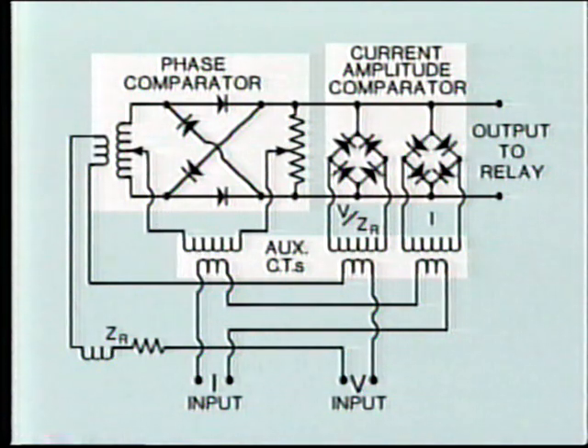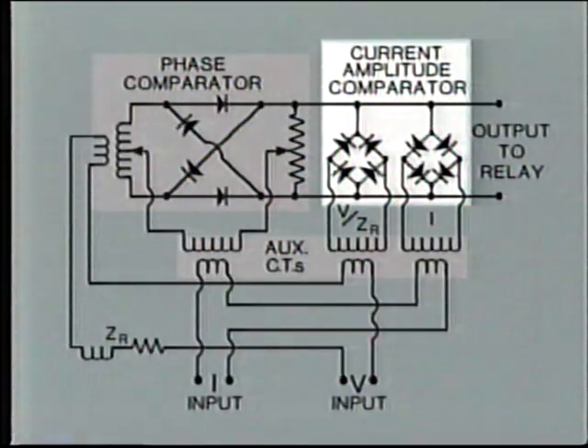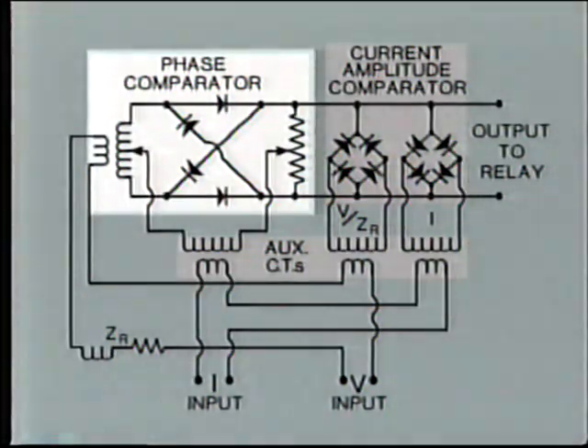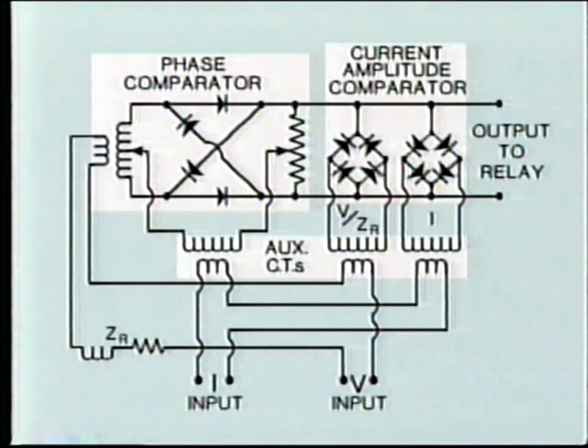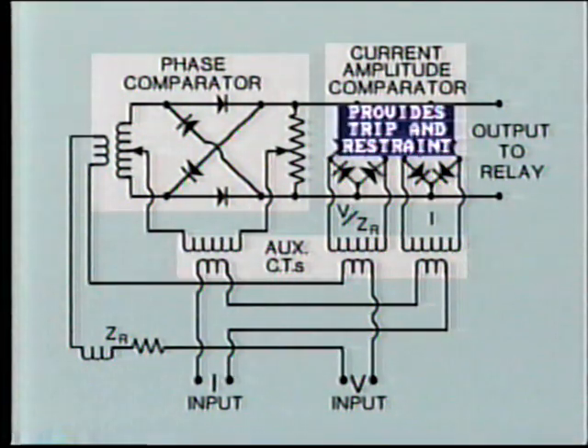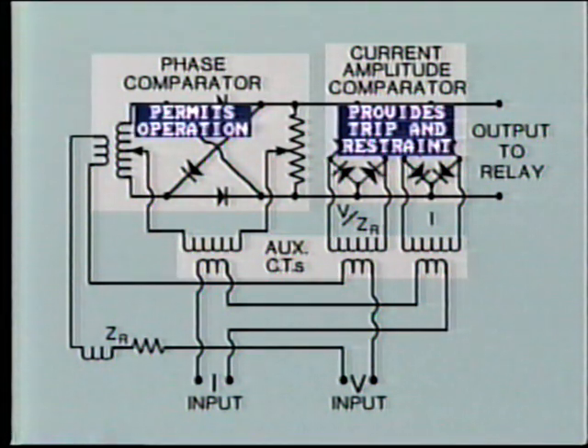And here is another arrangement that combines amplitude comparison with phase comparison using rectifiers. The amplitude side provides trip or restraint, while the phase comparator is a permissive, allowing operation only within a specified phase angle. A more precise method of controlling operation of the distance relay is by use of a sequence comparator.